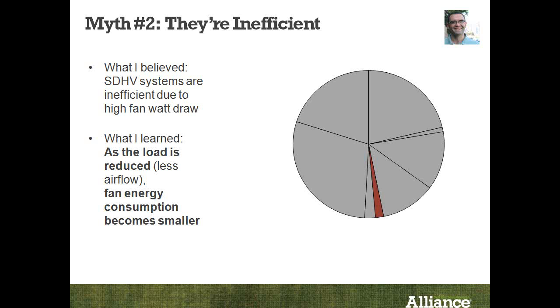We've heard before that they're very inefficient due to the high fan watt draw. If you're talking specifically about small diameter high velocity duct systems, they can have very high static pressures. Let's say 1.2 to 1.5 inches and above is basically a small diameter high velocity duct system, and at 1.2 inches of water column, there can be a very high fan watt draw. So when these systems came out in the 1990s, you had a house that was fairly inefficient for the most part, and you had a very large airflow.